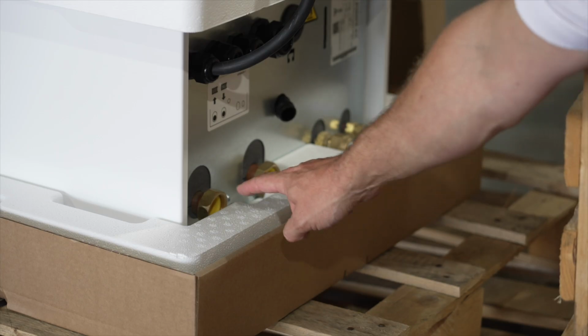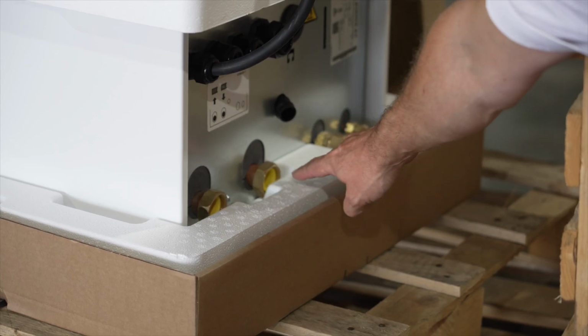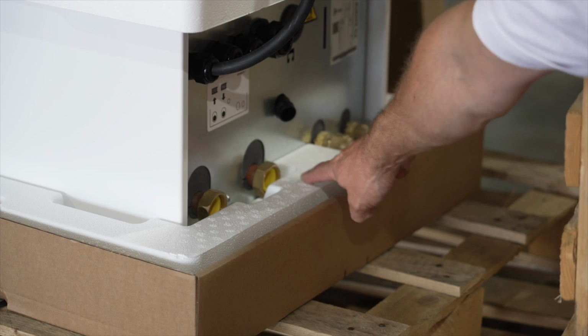Before you mount the unit, the first thing you must do is remove the yellow blanking plugs from the pipework connections at the bottom of the unit. These plugs are easily forgotten and missed on installation, as they can be quite difficult to see once the unit is mounted to the wall.